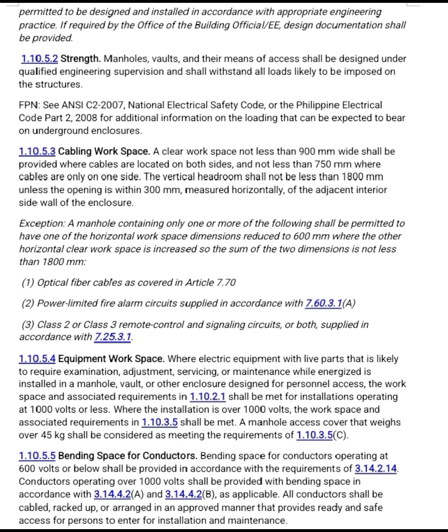1.10.5.3 Cabling workspace. A clear workspace not less than 900 mm wide shall be provided where cables are located on both sides, and not less than 750 mm where cables are only on one side. The vertical headroom shall not be less than 1800 mm unless the opening is within 300 mm, measured horizontally, of the adjacent interior side wall of the enclosure. Exception: a manhole containing only one or more of the following shall be permitted to have one of the horizontal workspace dimensions reduced to 600 mm where the other horizontal clear workspace is increased, so the sum of the two dimensions is not less than 1800 mm.